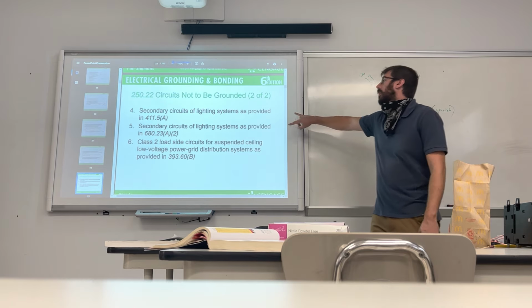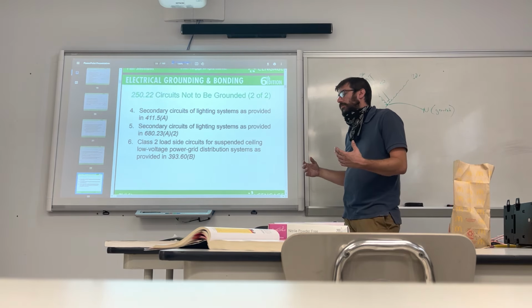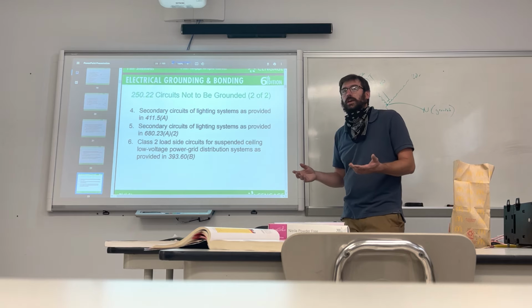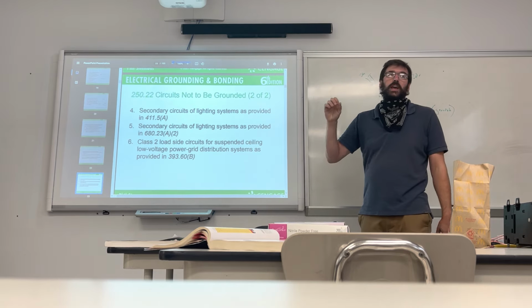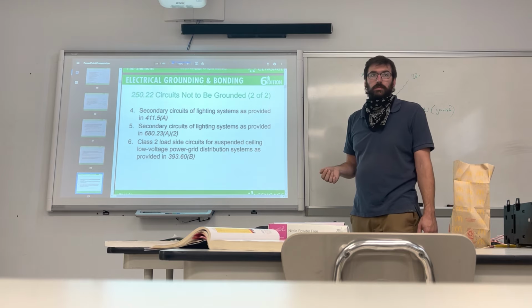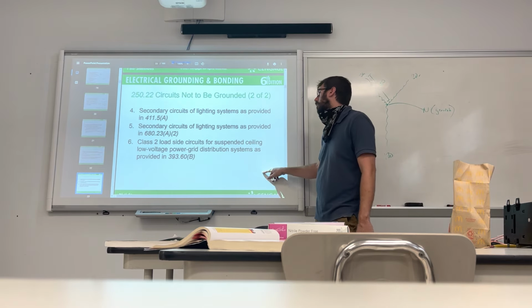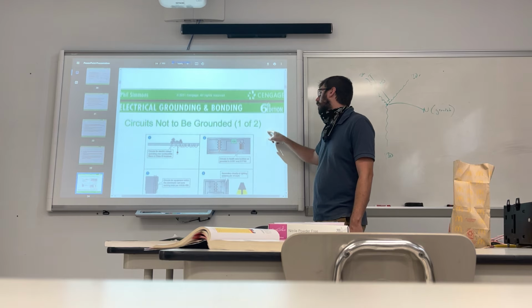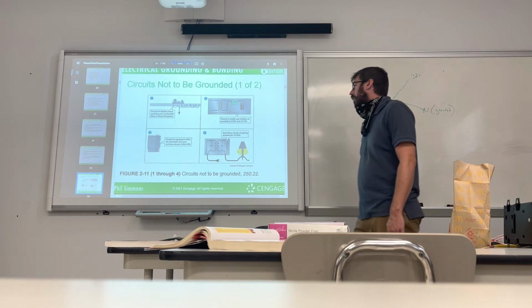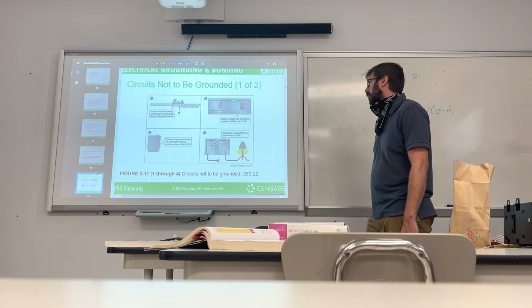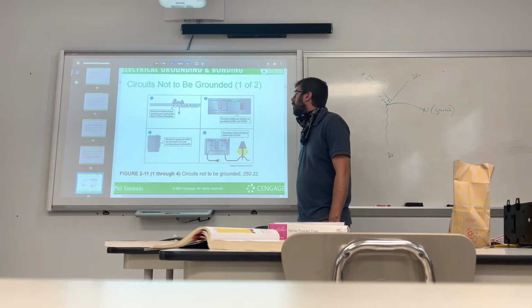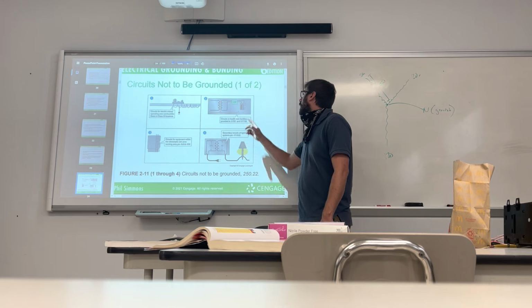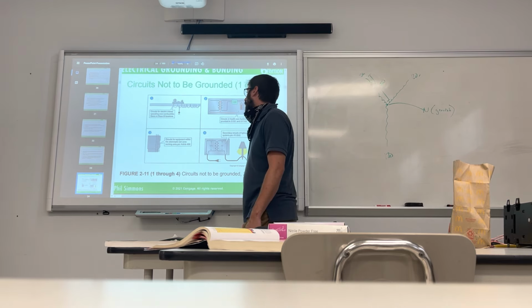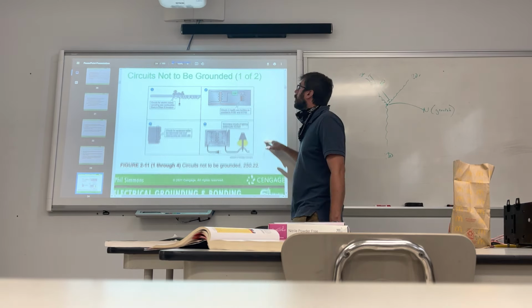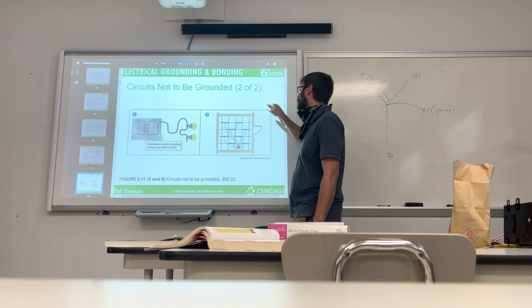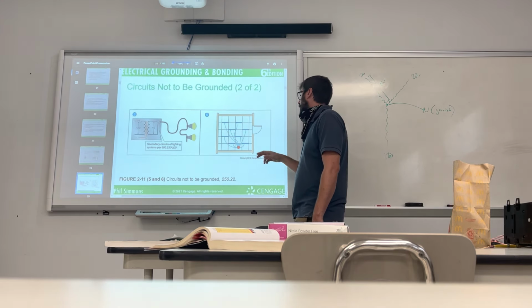So just understand that on a lot of lighting systems, like for lamps, very small things feeding just one small light, if it's less than 30 volts, they're not going to require you to ground it. That's what that means, just so we know. And once again, that's a readout of circuits that don't have to be grounded. Once again, that's the light I was talking about: circuits for the crane, healthcare and life support, and the cells. Cool. This is secondary light circuits.